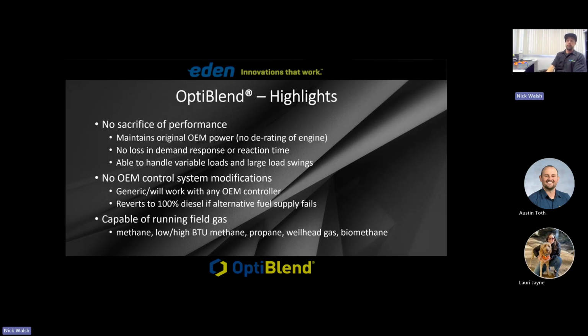We're able to handle variable load swings, large load swings, block loads, whatever you want to call them. This comes up a lot in the oil fields when they're tripping pipe, for instance, pulling the drill string out of the ground. The engines will load up, all four engines will load up 80 to 100% until the drill string's pulled out. And then once it's out of the ground, the load comes all the way back down to near zero. So we have these large block loads on the engines, and our kits are able to sense that and make adjustments.